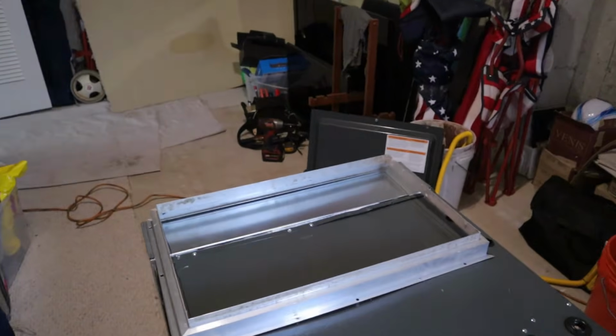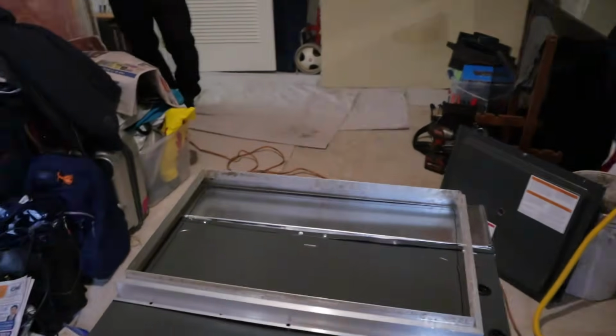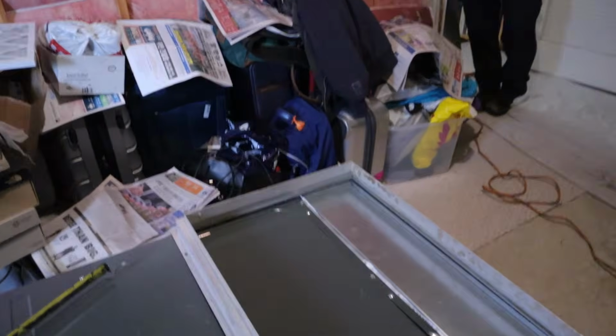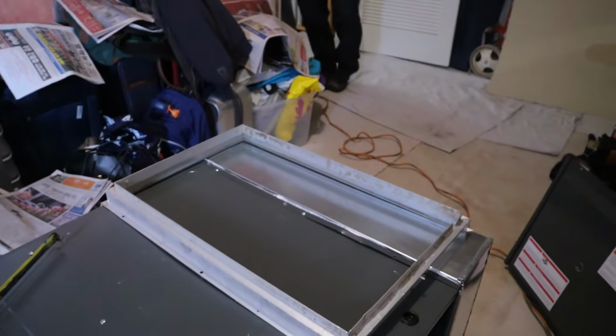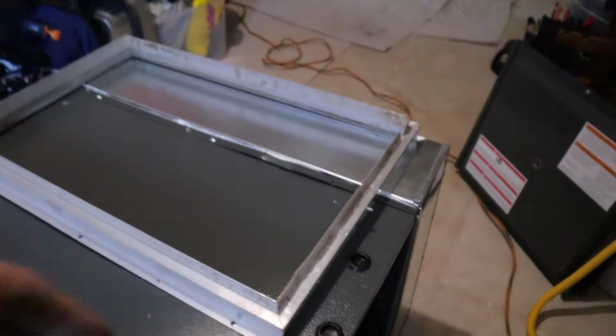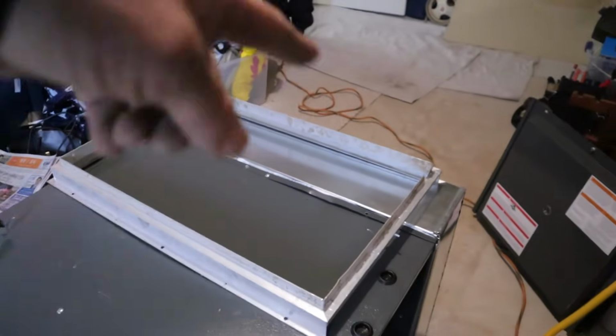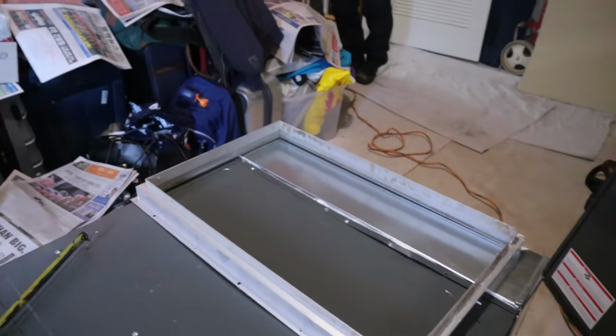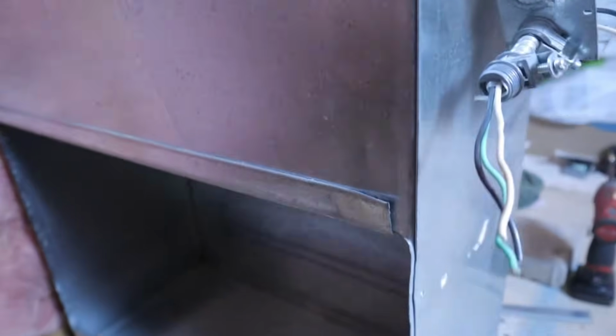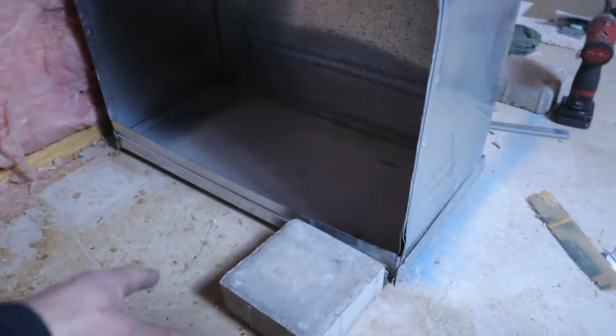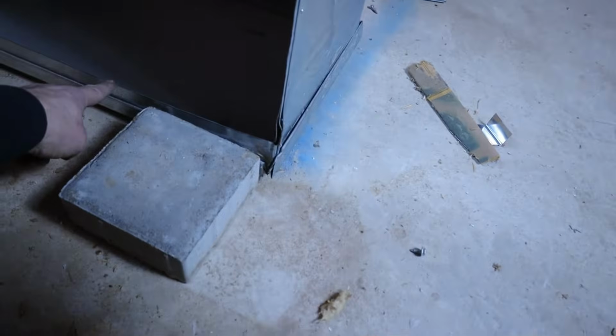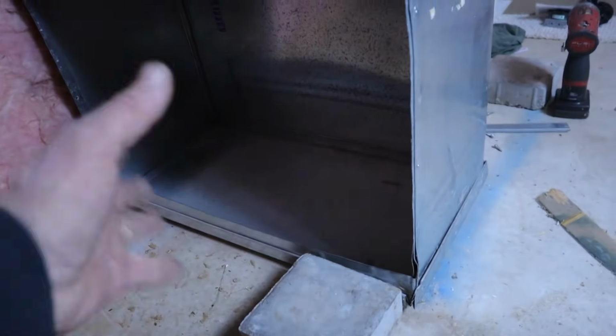Alright, so what we're doing now is we have to cut the hole for the return duct into the side of this. So this is a filter track that was existing. We're going to put that back in. So that's about the size of the hole we need. But what we're doing is over here, we measure how far this hole is up off the floor. All right, so I got about 3 inches there.